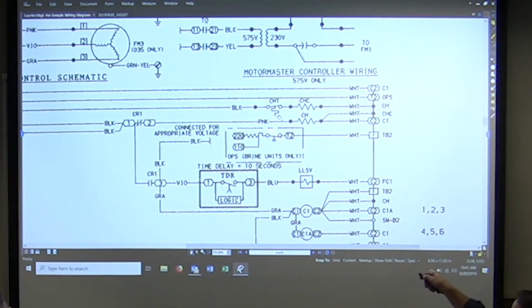What is this kind of a switch? Pressure. So pressure, that's a symbol for pressure. We have this little guy that's more of an electronic switch of some type, okay? And in this case, that's the time delay relay. What is this symbol? Liquid line solenoid valve. Okay, so it's a solenoid. In this case, this is the liquid line solenoid that opens and closes to allow the refrigeration process to work.